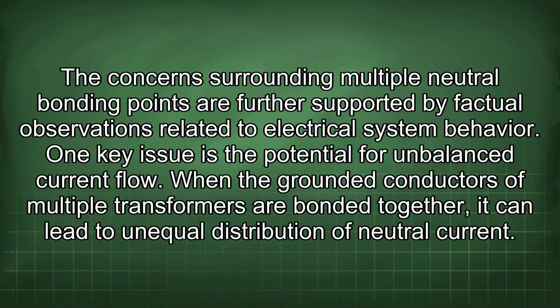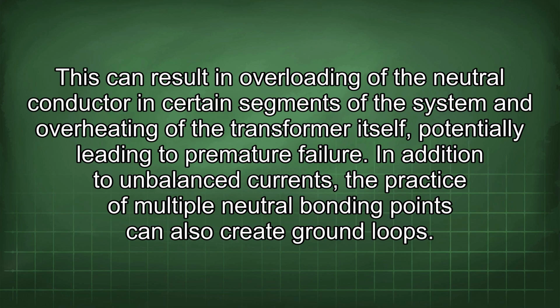The concerns surrounding multiple neutral bonding points are further supported by factual observations related to electrical system behavior. One key issue is the potential for unbalanced current flow. When the grounded conductors of multiple transformers are bonded together, it can lead to unequal distribution of neutral current. This can result in overloading of the neutral conductor in certain segments of the system and overheating of the transformer itself, potentially leading to premature failure.